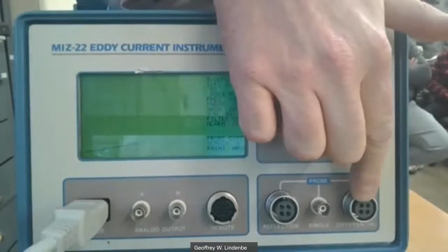Depending on what type of probe you're using, you have to plug your cable into the correct connector. But not only do you have to do that, you also have to tell the machine which connector to look at. Right now probe is set to diff, meaning it's looking at this differential probe port.